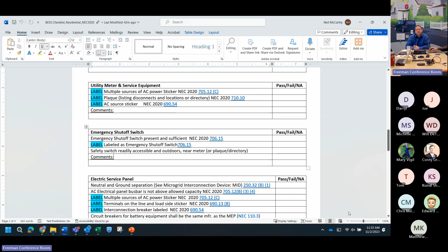And then down at the electrical service panel, there's a problem that occasionally shows up with the neutrals and the grounds. I know you're all experienced battery installers, but I need to tell you that you can only have one point where the neutral and the ground come together on any site. Usually that's going to move over to the hub, to the MID, the microgrid interconnection device, which is where that interconnection is going to be.